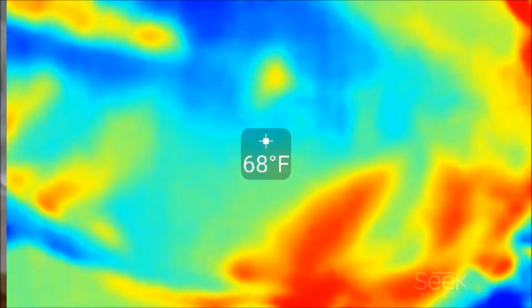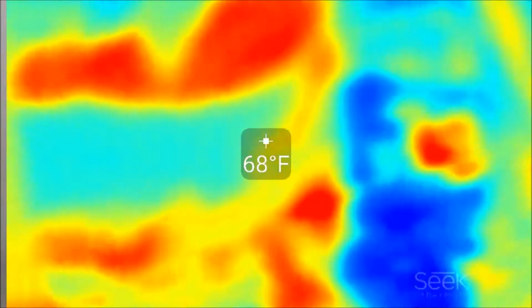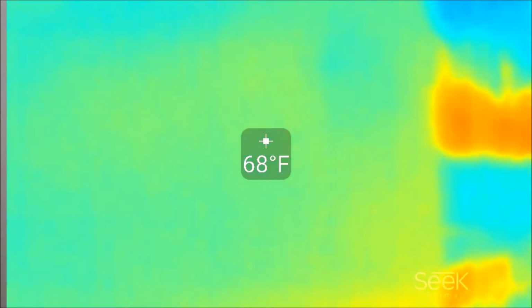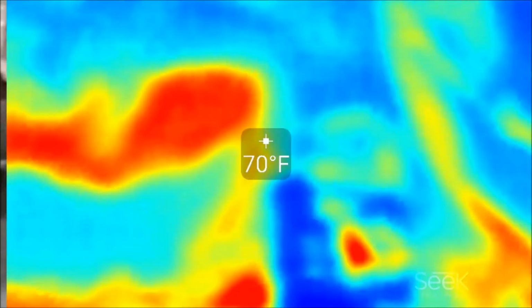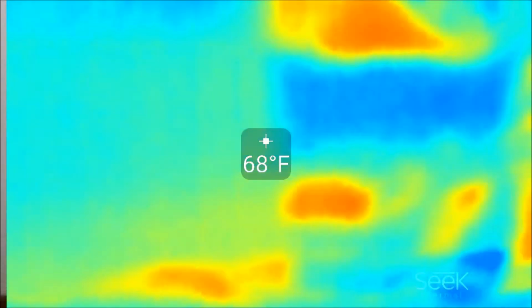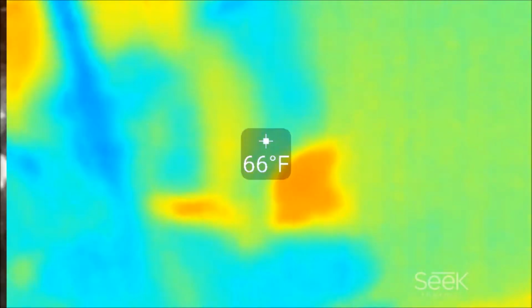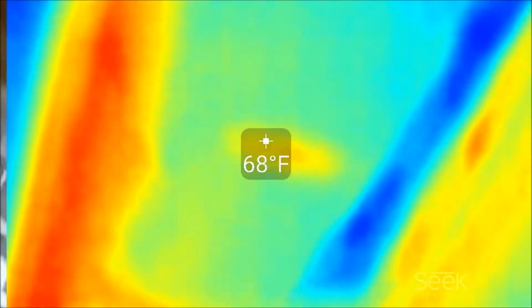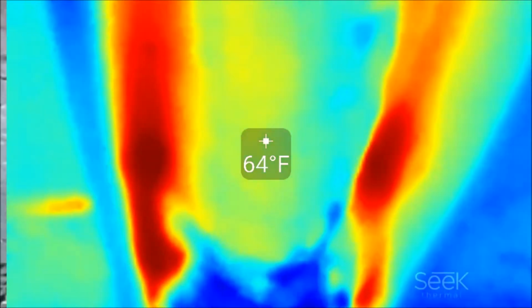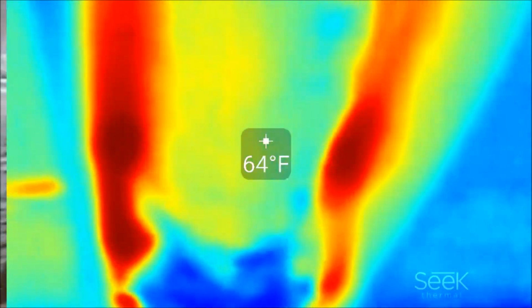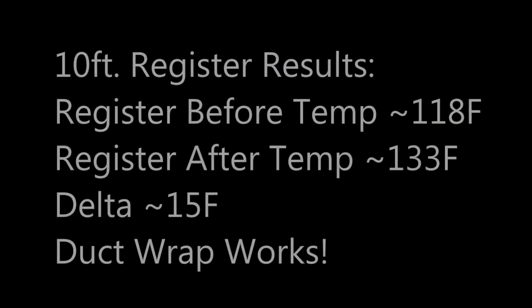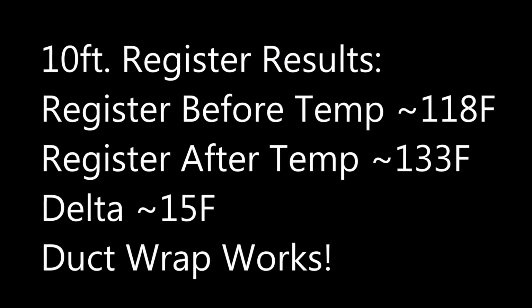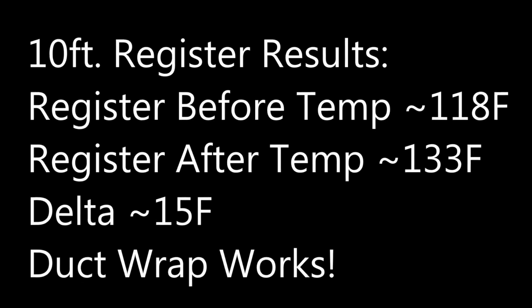So basically I was paying to heat my basement without the duct wrap installed. You can obviously see it's a significant difference in what an unwrapped and a wrapped duct will do temperature-wise. I've got a little bit of work still left to do to snub out all these little hot spots back at the register. So here are the results from the register test. Before, the register was about 118 degrees, after 133, so that's a 15 degree difference in heating for that register.